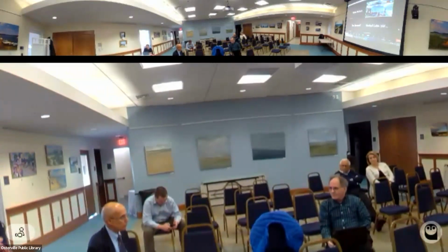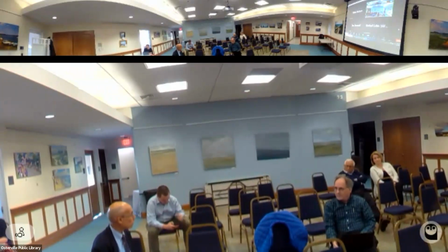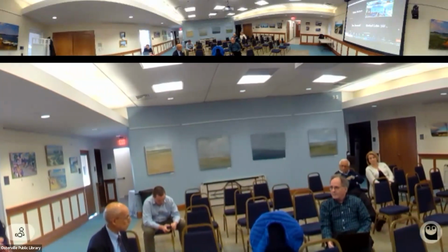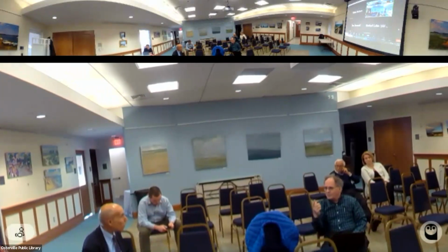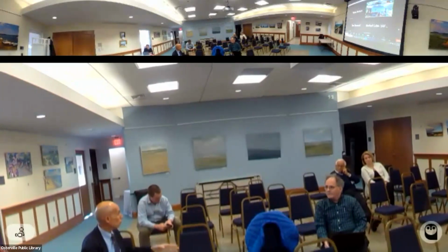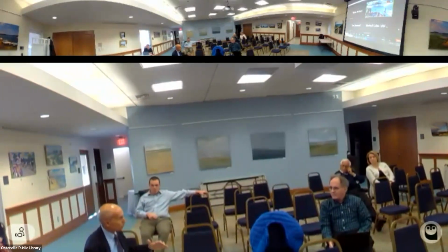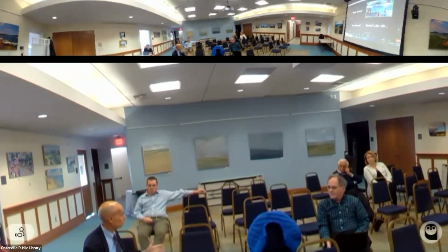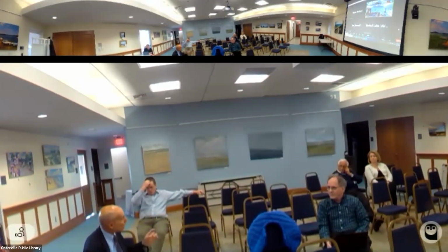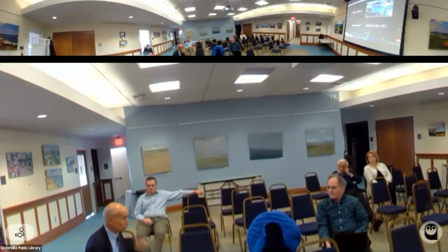Okay. It's an area we put keen focus on because they do require a fairly large excavation, given the size of the vaults. So the size of the vaults, they're 32 feet long. Did I hear you say that? Yes, let me send you drawings, but generally roughly 32 feet, roughly 8 foot tall by about 6 foot wide. And by the way, every circuit gets its own splice vault. Okay, and that's for safety.